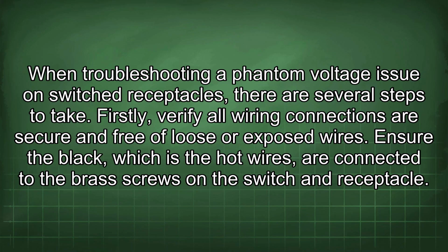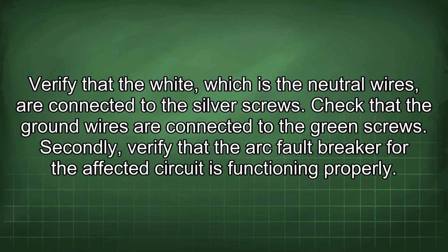When troubleshooting a phantom voltage issue on switch receptacles, there are several steps to take. Firstly, verify all wiring connections are secure and free of loose or exposed wires. Ensure the black wires, which are the hot wires, are connected to the brass screws in the switch and receptacle. Verify that the white wires, which are the neutral wires, are connected to the silver screws. Check that the ground wires are connected to the green screws.